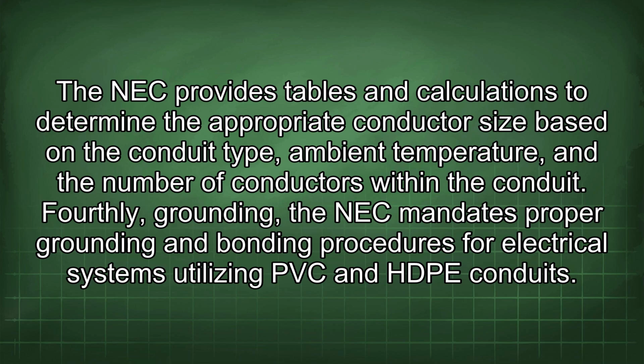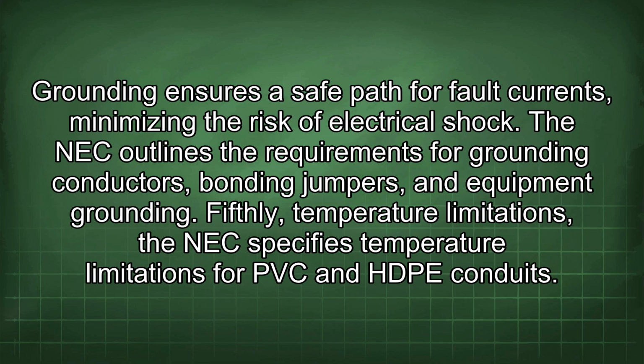Fourthly, grounding. The NEC mandates proper grounding and bonding procedures for electrical systems utilizing PVC and HDPE conduits. Grounding ensures a safe path for fault currents, minimizing the risk of electrical shock. The NEC outlines the requirements for grounding conductors, bonding jumpers, and equipment grounding. Fifthly, temperature limitations. The NEC specifies temperature limitations for PVC and HDPE conduits.